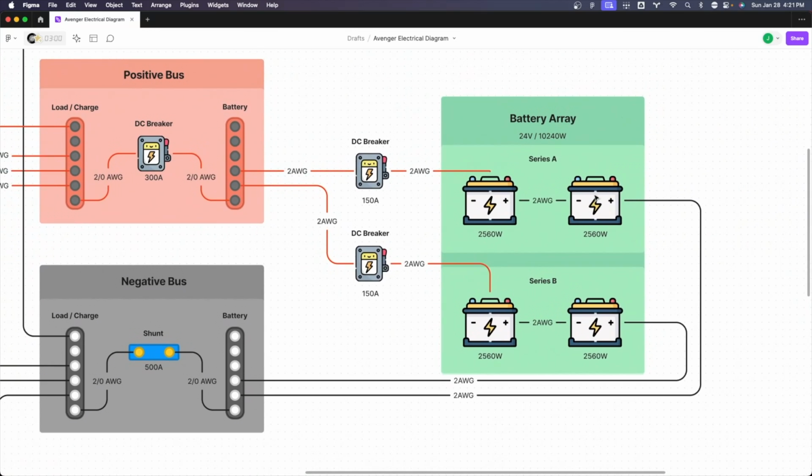This takes us over to the battery array. Like I said earlier, this is a 24 volt array where I'm taking two series and paralleling those two series together into this bus. And so I left myself some room here. That's why I got the bus bars that I did. In case in the future I want to sacrifice that bed altogether, I could add two more series of two into this and still be within spec with all the wiring that I've put in up to this point.